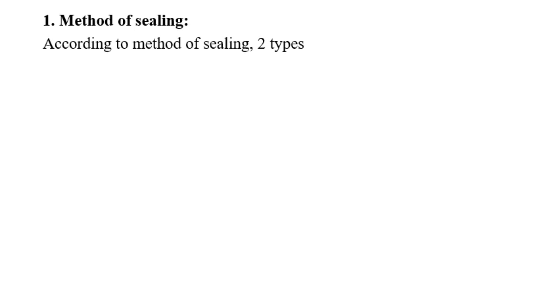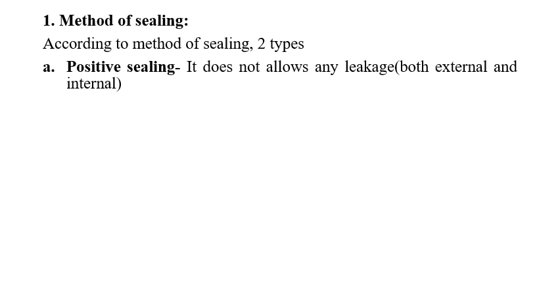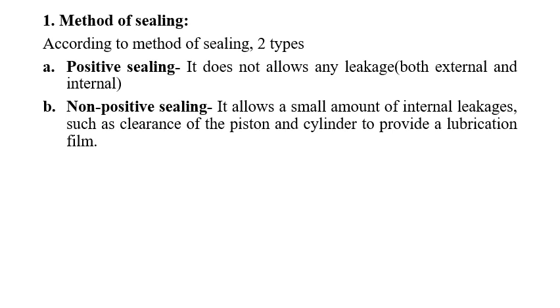First classification — method of sealing: according to the method of sealing there are two types: positive sealing and non-positive sealing. In case of positive sealing, these sealing elements do not allow any leakage, either internal or external. In case of non-positive sealing, these sealing elements allow a small amount of internal leakage — for example, the clearance between the piston and cylinder — to provide a movement lubrication film between them.